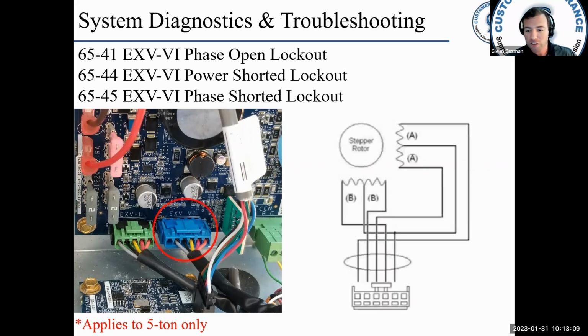Okay, it looks very similar. It is still 5 wires, but notice on the plug, you have 6 pins, although 1 pin is left blank, so you cannot interchange them. Now the EXVs are similar, but they are not interchangeable. So if I have a heating EXV, I cannot put it in place of the vapor injection EXV, and vice versa. Okay.